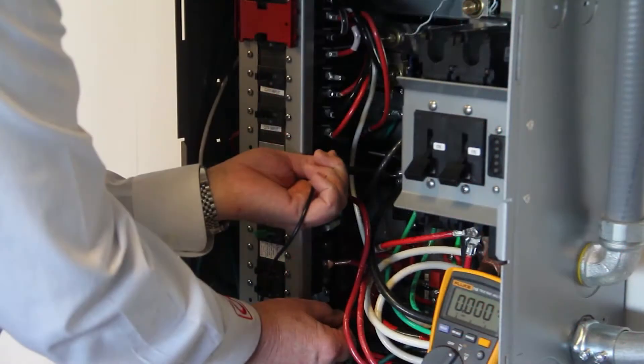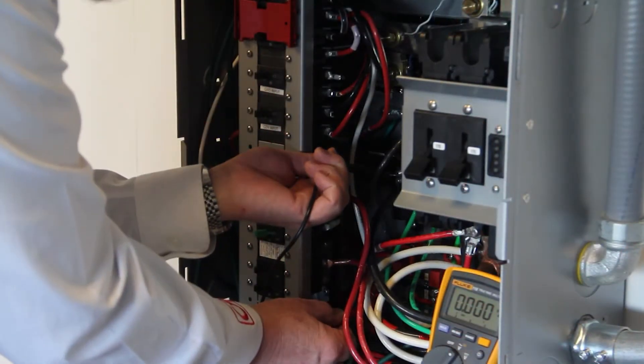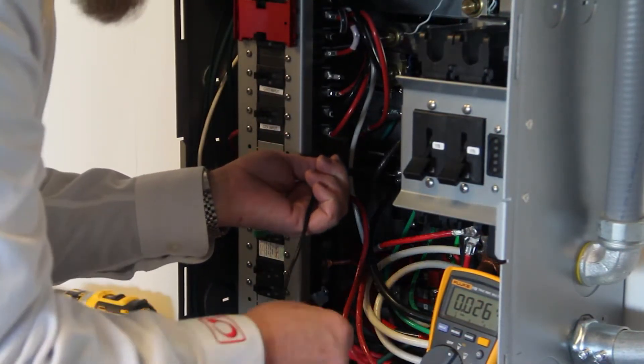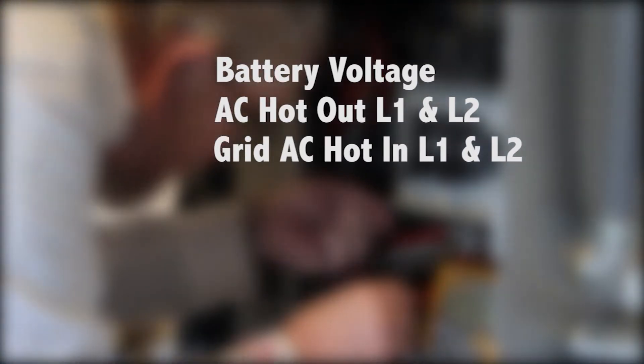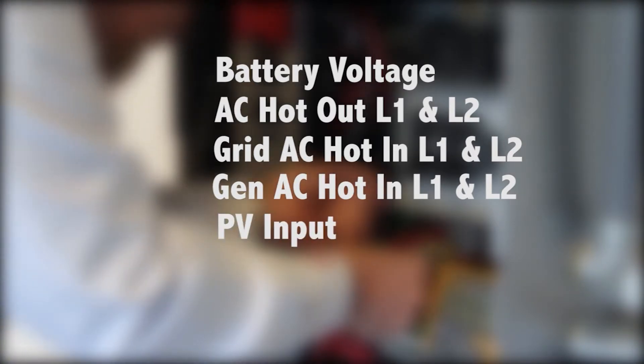Verify no voltage is present from the terminals: battery voltage, AC hot out L1 and L2, grid AC in L1 and L2, generator AC in L1 and L2, PV input.